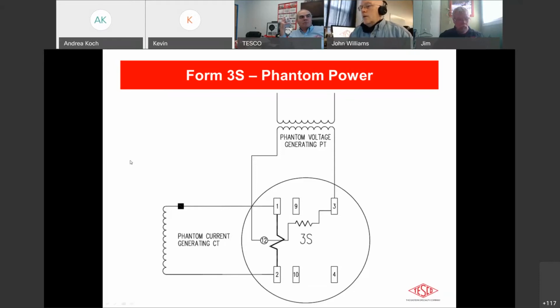So one thing to keep in mind when you're applying a 3S meter on a meter test board, again, we typically have been defaulting the service to 120 volt, which would be a potential transformer application for the 3S. Reason we do that is typically these are single voltage meters. And if we default it to 240 and you have a 120 volt meter in there, bad things are going to happen to the meter. But of course, you could always change those defaults if you're only using the 240 volt 3S meter.